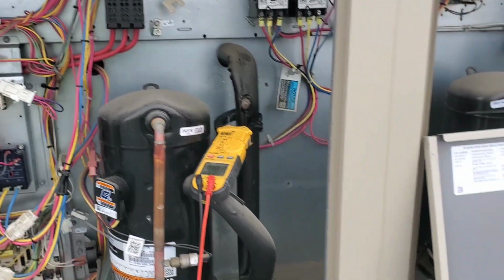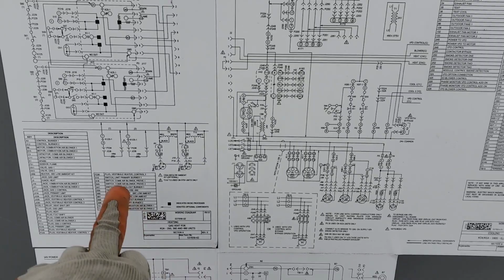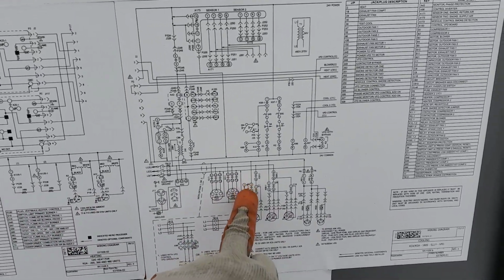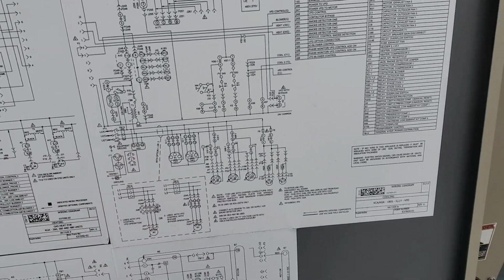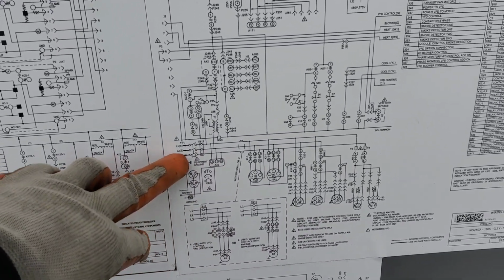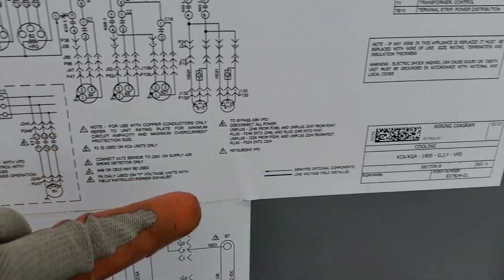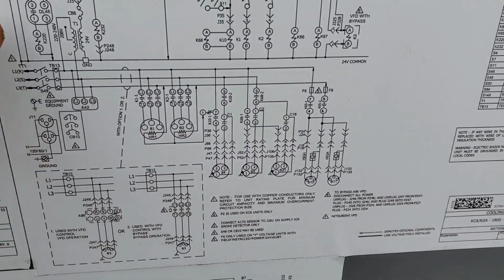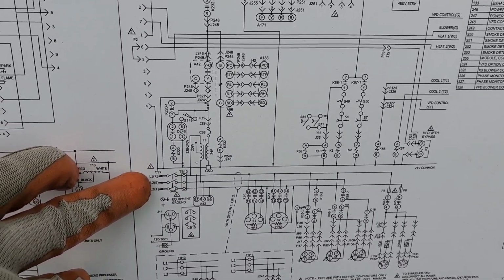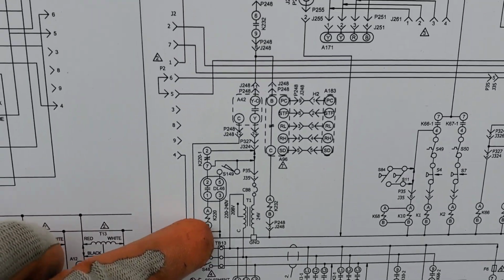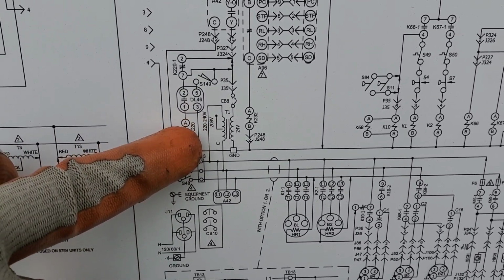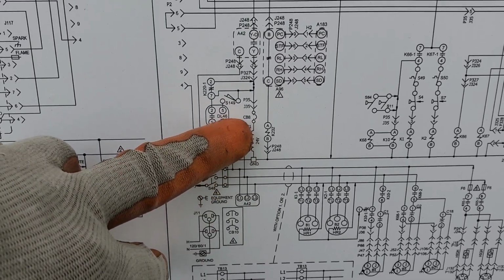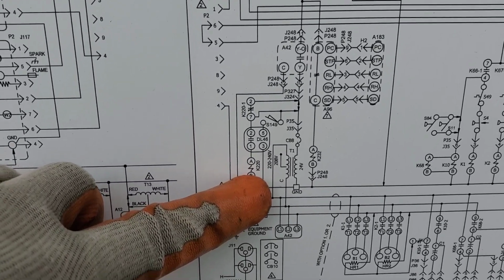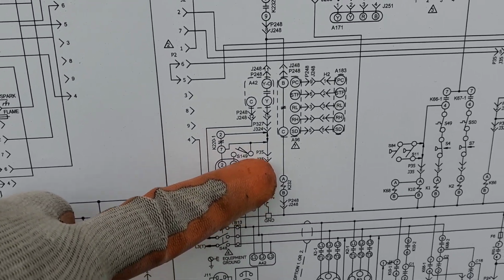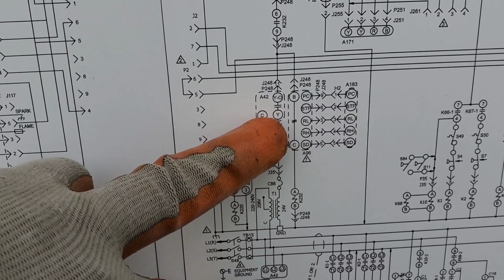Okay, let's try to find out with our wiring diagram what is the issue. On the Lennox units, usually they separate their heating wiring diagram and the cooling wiring diagram, but this is the voltage issue. So we're gonna just trace it through the cooling wiring diagram. But we are just tracing the voltage issue because there is no voltage on the R. Okay, so here is our main transformer, 24 volt secondary, and okay, if you follow the 24 voltage line, and this is directly connected to Y here.